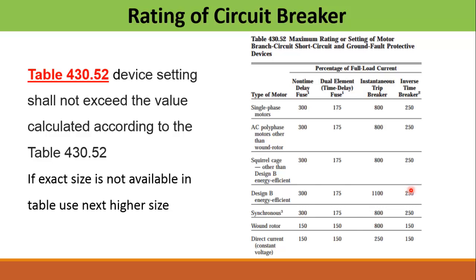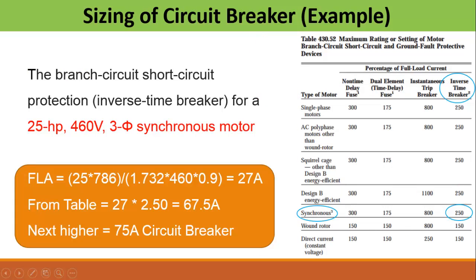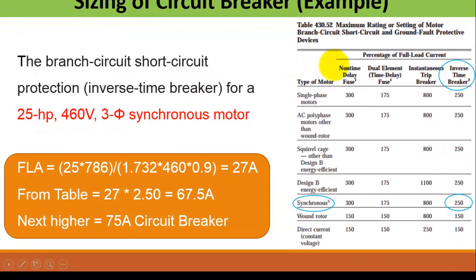Let's solve an example to understand how to properly size a circuit breaker. The motor type is a three-phase synchronous motor and the protective device is an inverse time breaker. From the table, this corresponds to 250% of the full load current. Using the power formula, the full load current is calculated to be 27 amperes. Multiplying by 2.5 gives 67.5 amperes. Since 67.5 is not a standard circuit breaker rating, we select the next higher standard size, which would be 70 or 75 amperes.